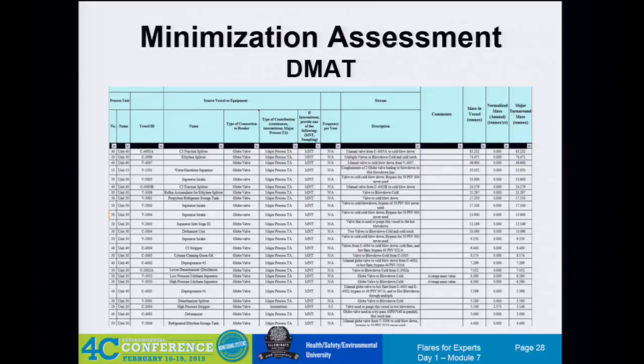It's also looking at control valves. We do a lot of pulling data out of control valves for percent open, then trending that to see if it's a control valve that opens once every 6 months and usually lines up with an upset - so it's acting more in an emergency capacity - or if it's something that's riding on the flare header all the time. So it's going through and being able to do that assessment of the connections.